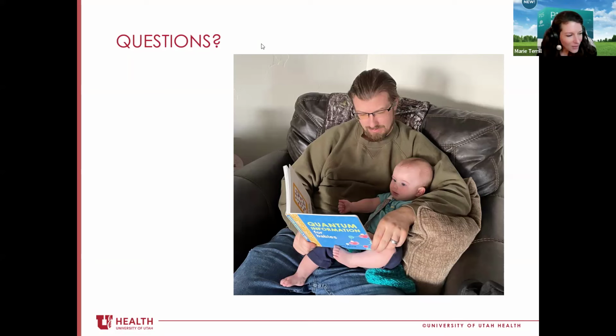And your graphs all look really good, but I'm stuck on the false positives in the babies that aren't having seizures at all. And so, it was pretty high in both of the newer types of the detection algorithms. What are your thoughts on that? I mean, if you're having babies that aren't having seizures and the software is telling you that they are, are you going to turn it off in real life? I mean, it's great for the other babies, but what's your practical use opinion on the false positives for the babies that are not actually having seizures?